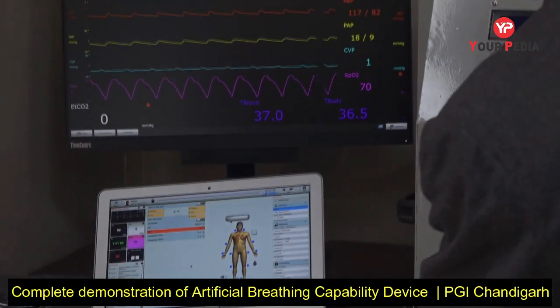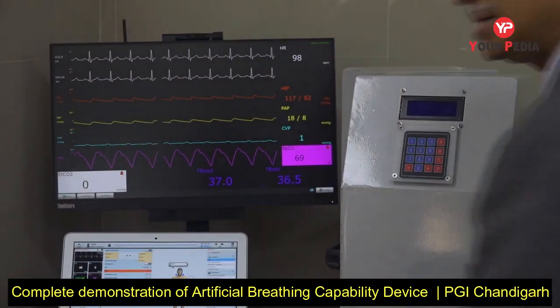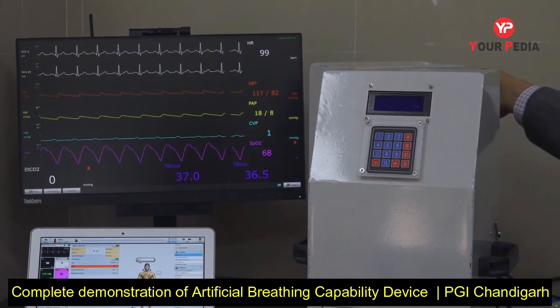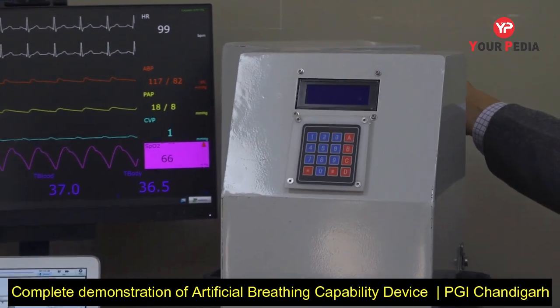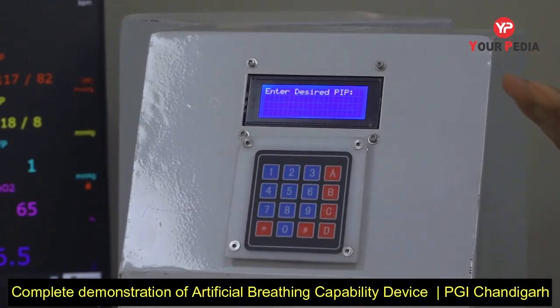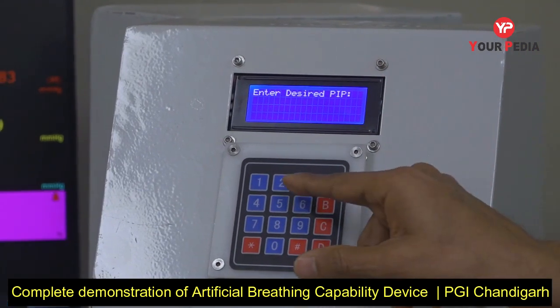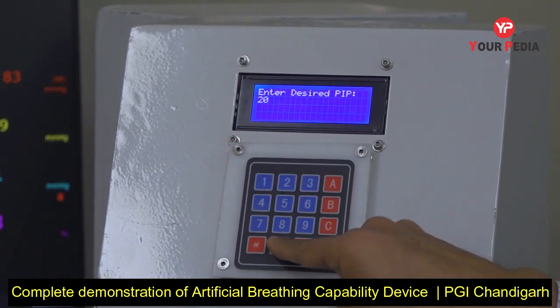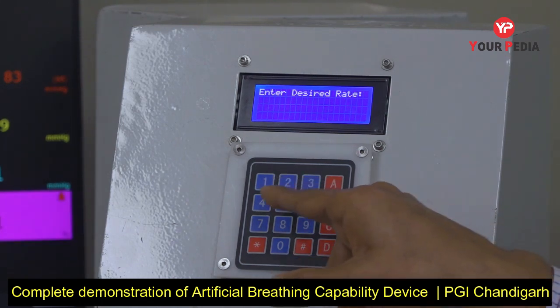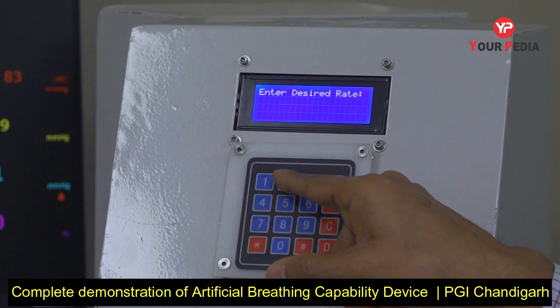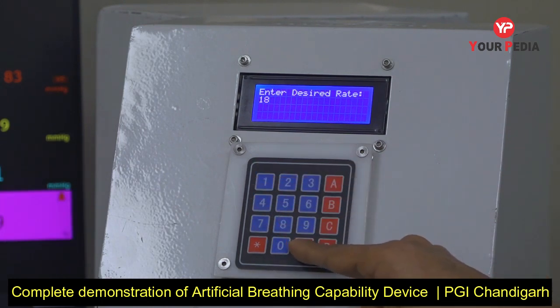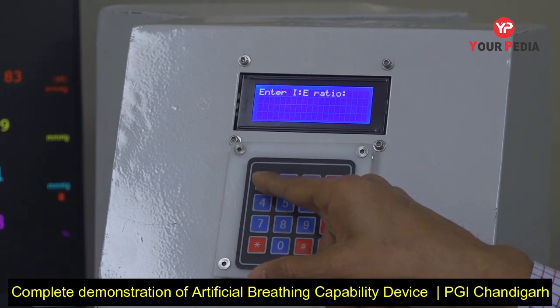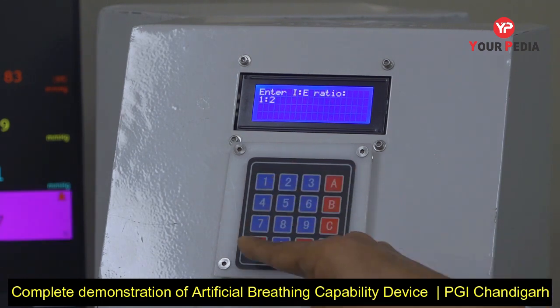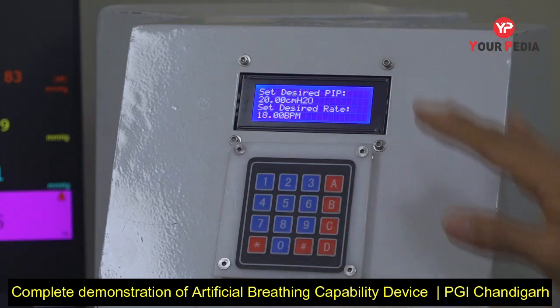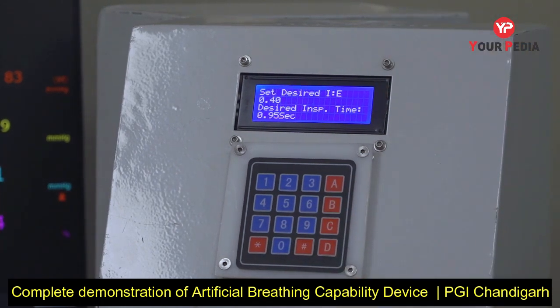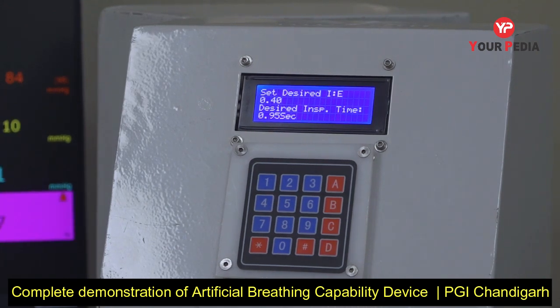So we will now set this patient to receive ventilation with this artificial breathing capability device, or ABCD. It's very simple to use. I switch this machine on and the machine displays its name, and thereafter it allows the user to enter a peak inspiratory pressure. So I'm setting a peak inspiratory pressure of 20, then a desired respiratory rate which can range anywhere from 10 to 60. Let's set it at 18, which is usual for an adult, and then an inspiratory to expiratory time ratio which I'm setting at 1:2.5. The machine immediately displays on the screen what has been set for the user to make a second check to know that it is exactly what he preferred.